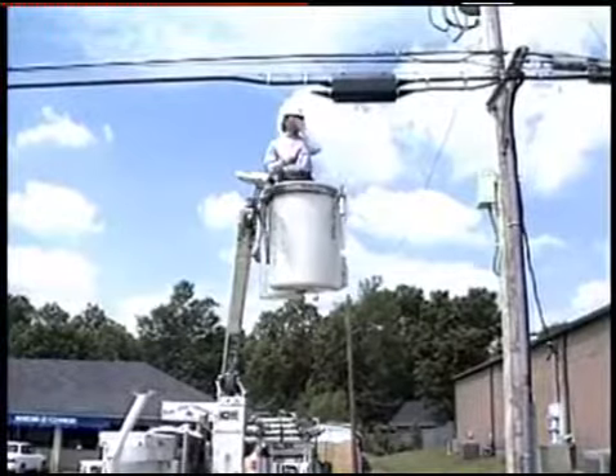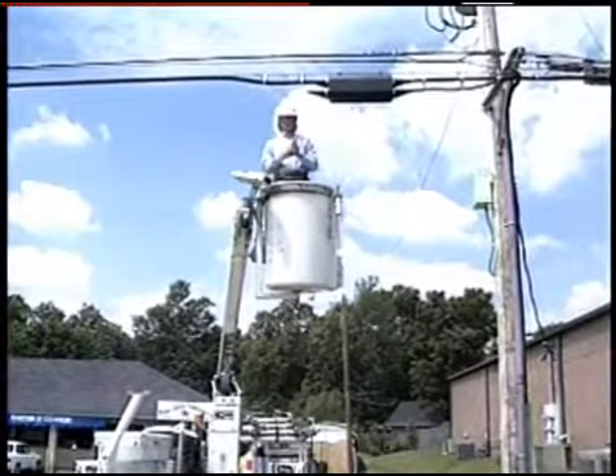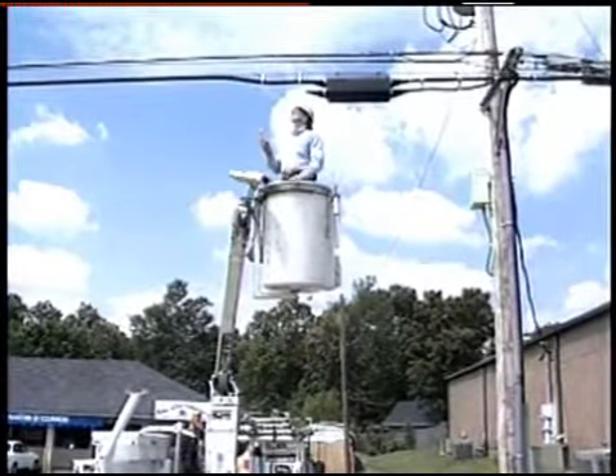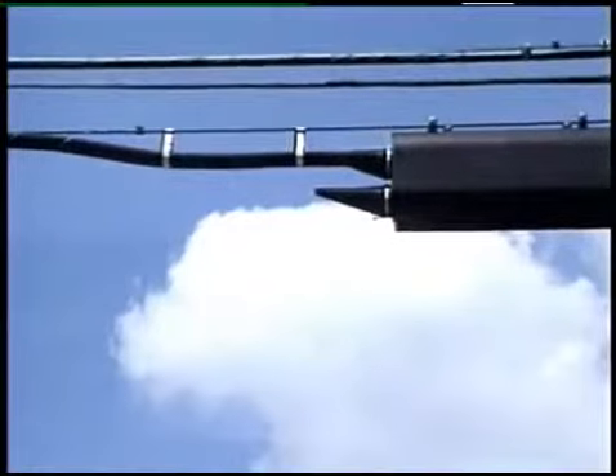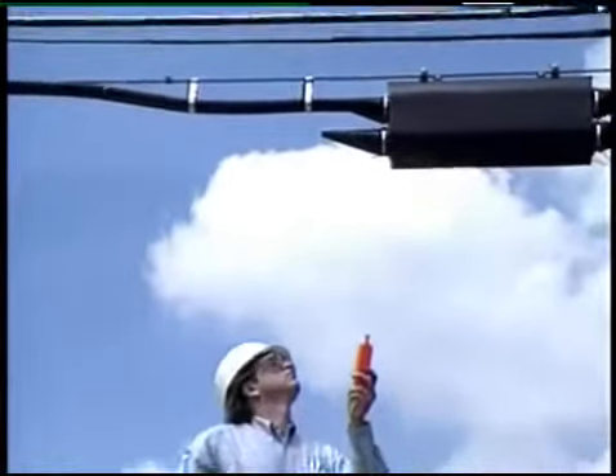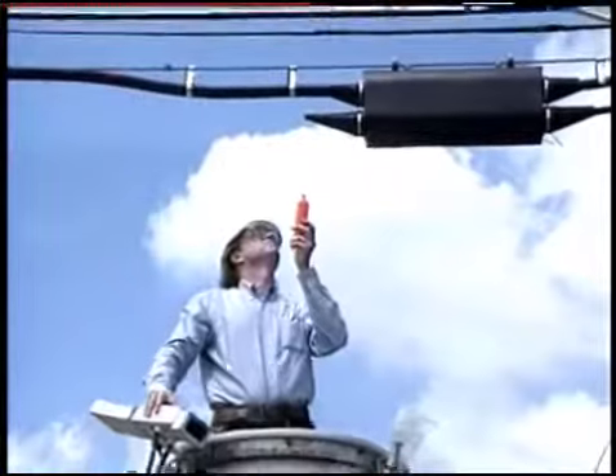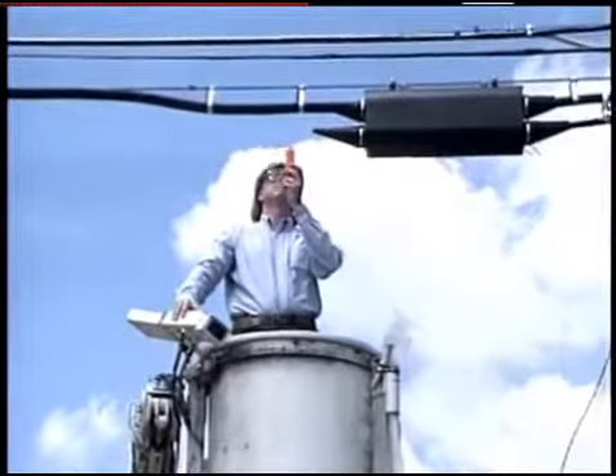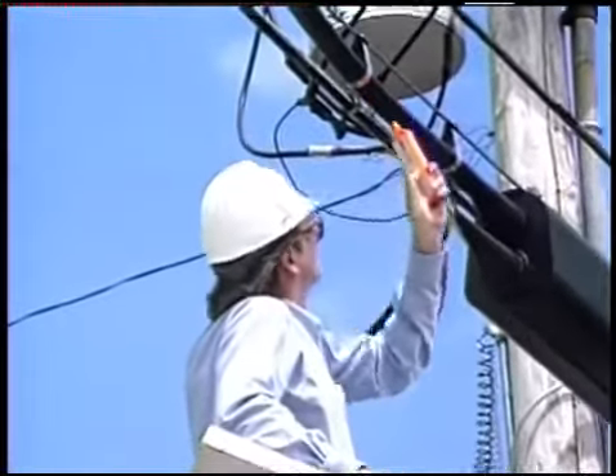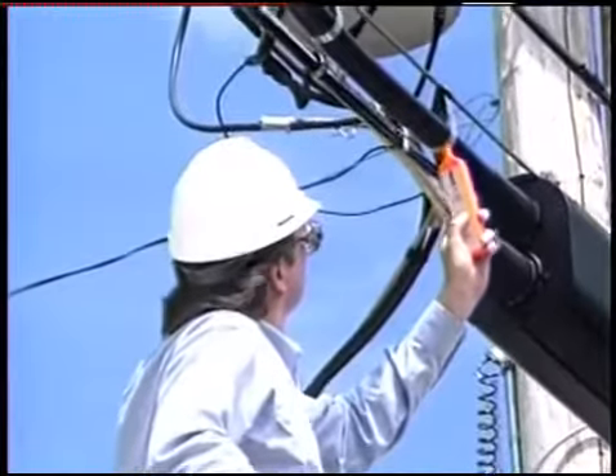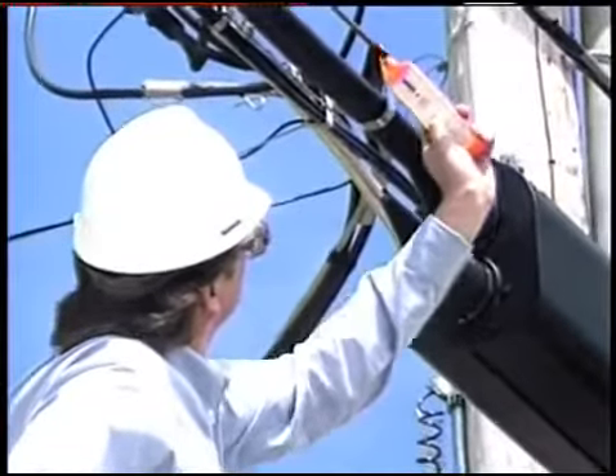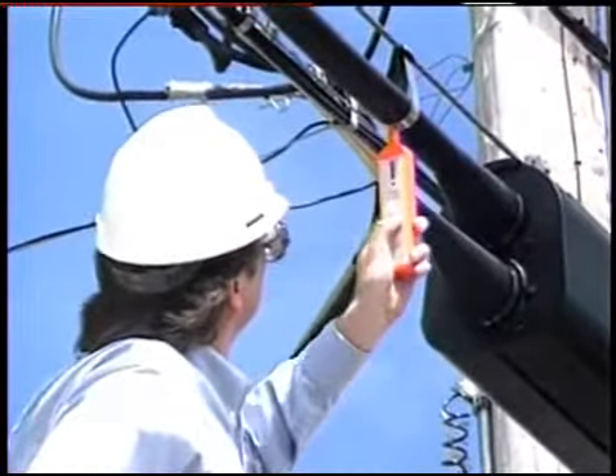When working aloft, an operator can make use of the shielding effect of the cable or strand being tested. As seen earlier, a grounded conductor will shield an operator from being coupled to an electrical field. Keeping this in mind, you would always approach the cable or strand to be tested from below. That way, the cable or strand itself will serve as a shield for the operator, avoiding the false indication that could otherwise occur.